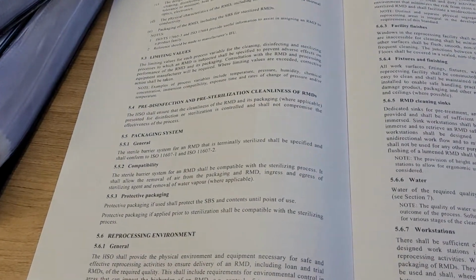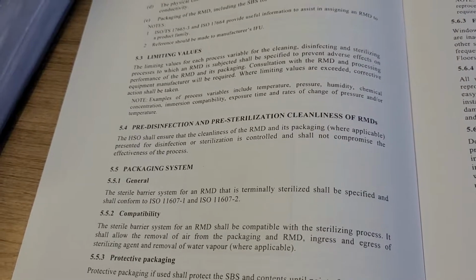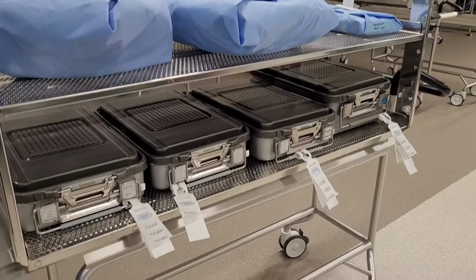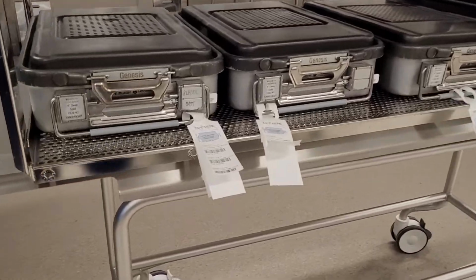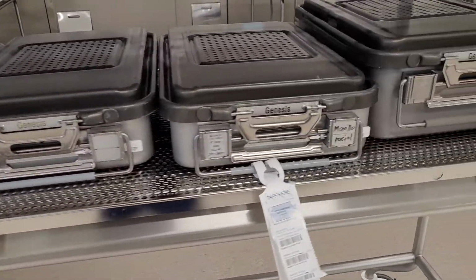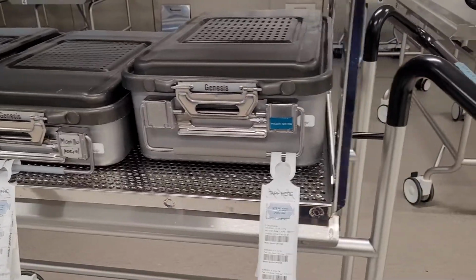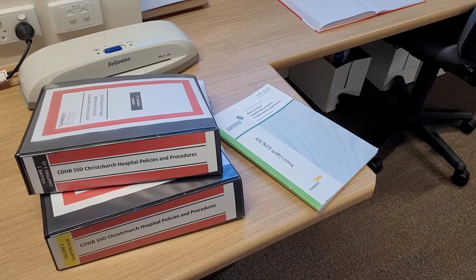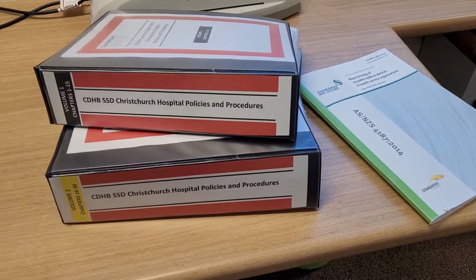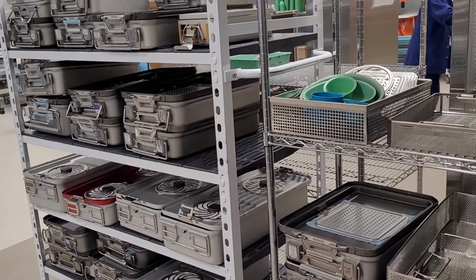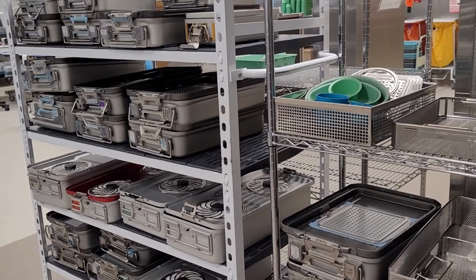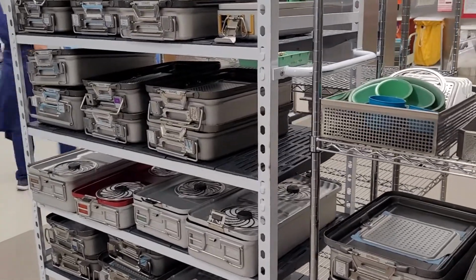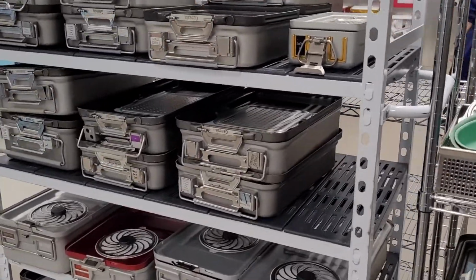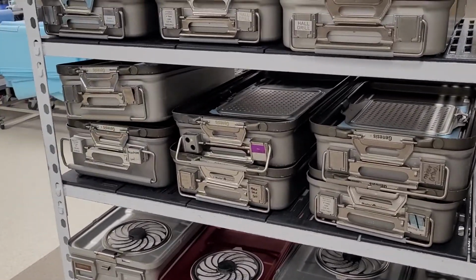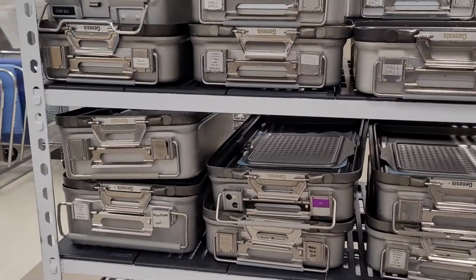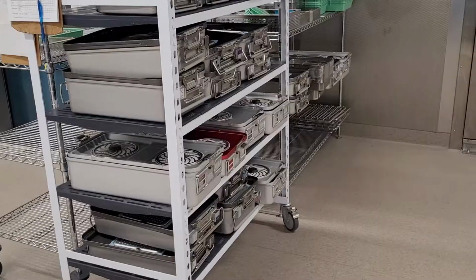Through the packaging requirements of this standard, protective packaging, the sterile barrier system or SBS, for an RMD, if applied prior to sterilization, must be compatible with the sterilizing process under Clause 5.5.3, page 14. Rigid containers such as Genesis sterilization containers are designed as a sterile barrier system to physically protect the contents and maintain their sterility, and not compromise the effectiveness of the process until the point of use.